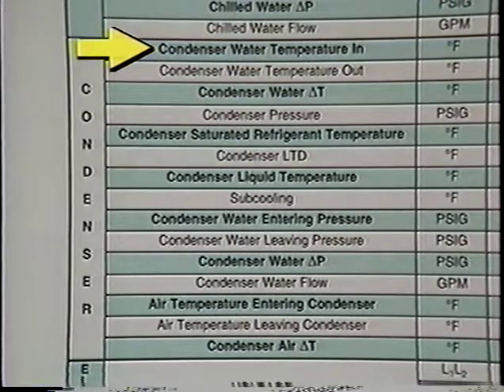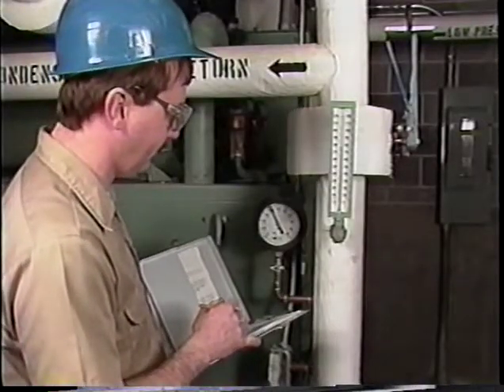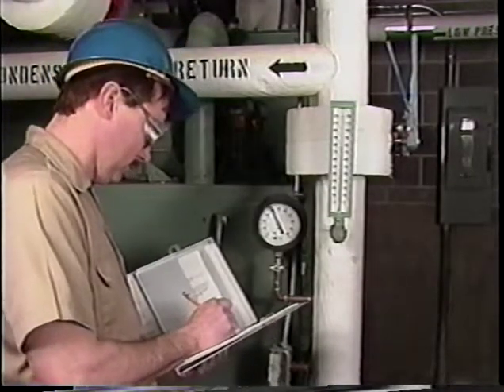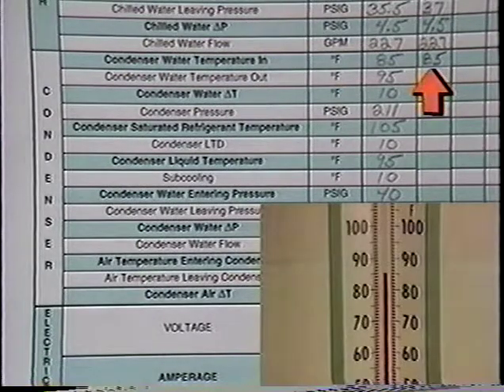Water temperature entering the condenser. This temperature should not exceed the design entering water temperature, and on most installations should not drop below 70 degrees Fahrenheit. Entering condenser water temperature can be up to 95 degrees. However, 85 degrees is more typical. If the entering water temperature drops too low, the condenser head pressure will not be high enough to supply refrigerant through the expansion valve.